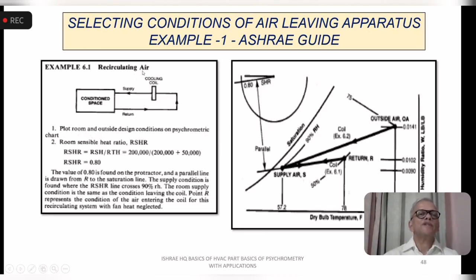If you have 100% recirculating air like this, there is no fresh air added. What is the conditioned space? Air is picked up, passed over the cooling coil and supplied. No addition of fresh air, which means you are supplying from the return air and the room is the same. So it goes over the coil and comes back. Recirculation, no fresh air added. Whereas if it is 100% fresh air, there is no return air added. That means you are treating the entire outdoor air, supplying it to the space and leaving it.